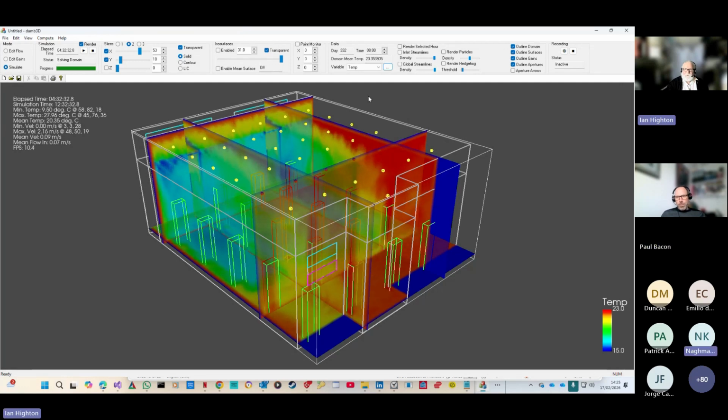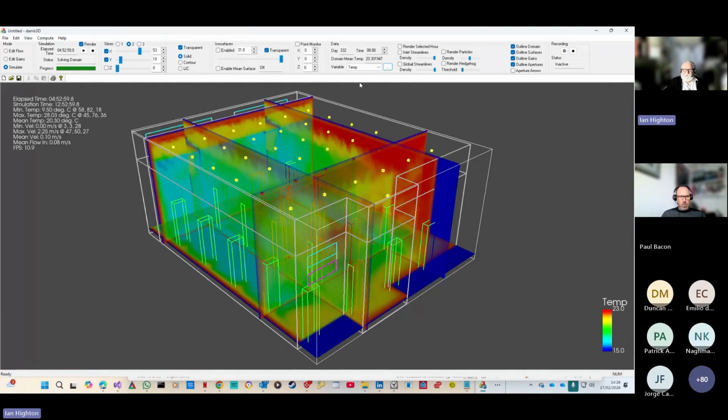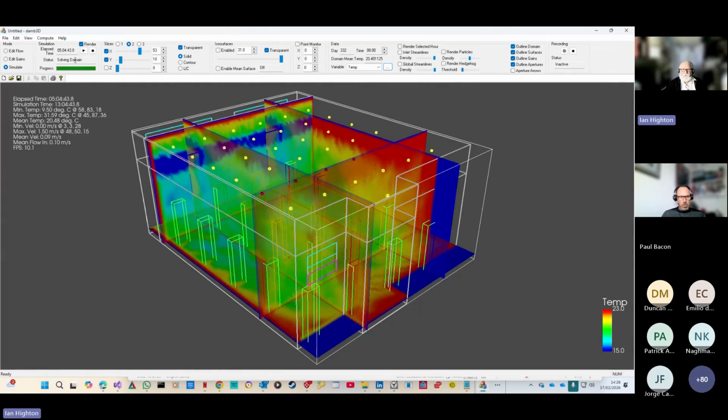From a TSD file. So all you have to do is make sure you have the correct output specifications in your TBD. Sorry, this is the building simulation, so the modeling bit of the total building. Just make sure you've got the right surface information being produced. So that's for solids like walls, that's just temperature, and for windows, we call them apertures, that's got to be the flow rate and the temperature. And then basically that all acts as the boundary condition for these calculations, which are then working forwards.